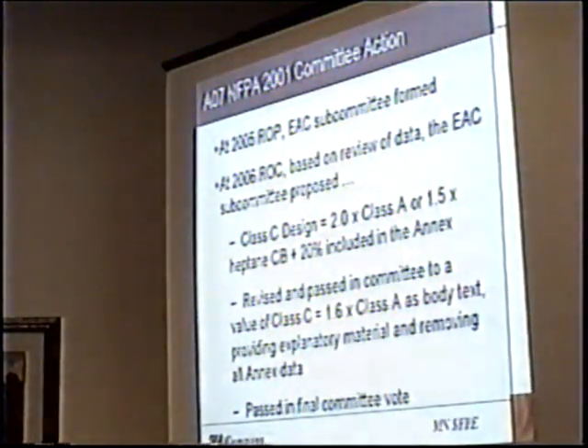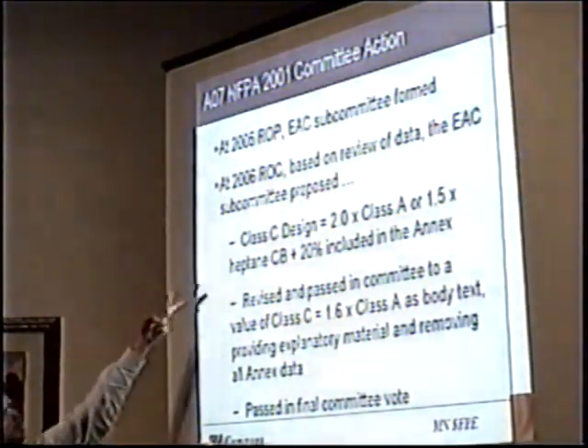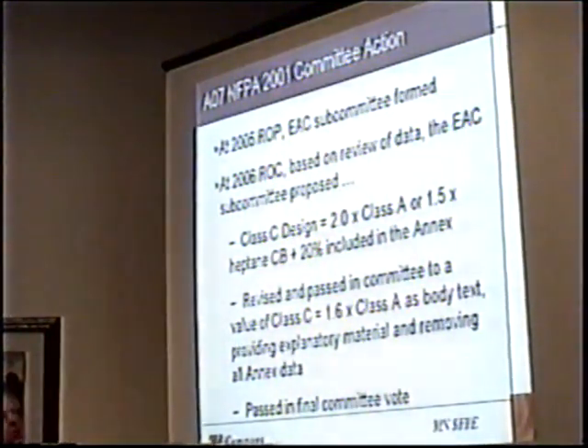In 2005, at the ROP, the Energy Augmented Combustion Subcommittee was formed to deal with this, reviewing the existing research that's been out there to date. In 2006, in the report on comments portion of the cycle, they basically reviewed the data. The subcommittee proposed this guidance: Class C design is 2 times the Class A, or 1.5 times the Class B heptane, whichever is higher, plus a 20% safety factor, and include that data in the annex. So it would be should data, not shall.